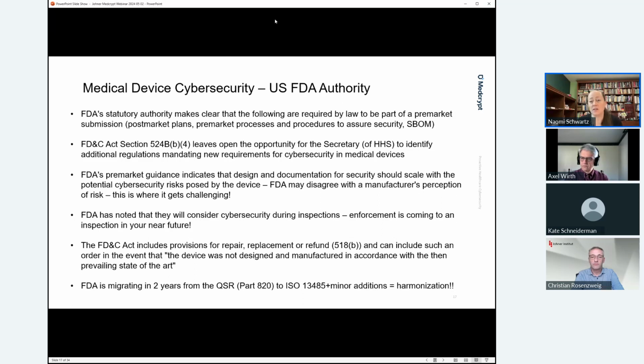So FDA has noted also that they're going to consider cybersecurity during inspections. A year ago, you might have heard Suzanne Schwartz talking about how the focus is on pre-market because enforcement is slow and it takes a long time, and making sure that devices are secure in the pre-market is FDA's best tool. That does not mean that they're not going to start enforcing, though. It just means that that's their second choice. But it's coming off the back burner. We know that enforcement is coming to an inspection in your near future. And we've heard directly from FDA that inspectional guidance for cybersecurity is being written. So you can expect that in future inspections, you may be asked very specific questions about your plans for cybersecurity in the post-market. And that's really important. FDA is just making sure that you're actually implementing the things that you have said that you're implementing.